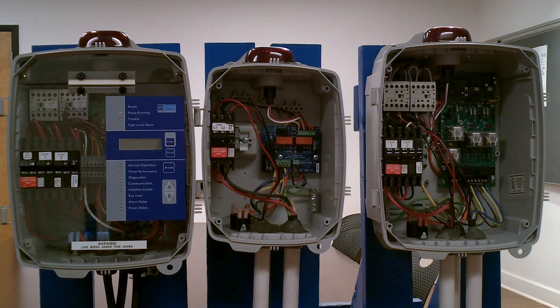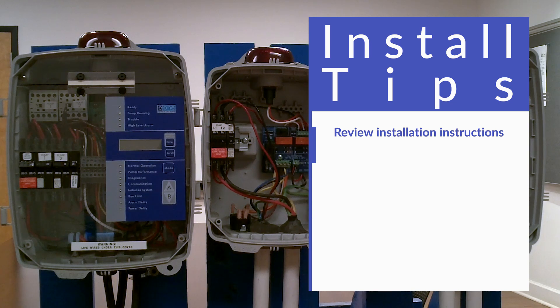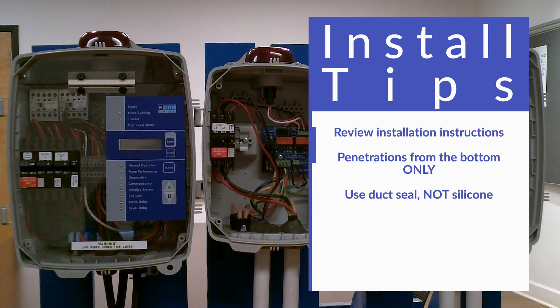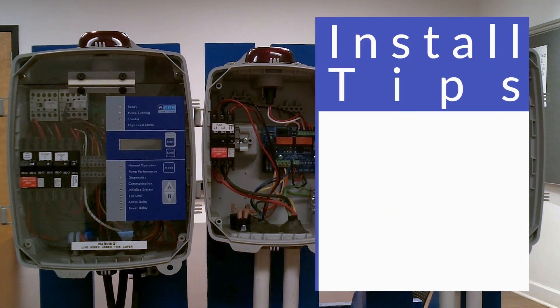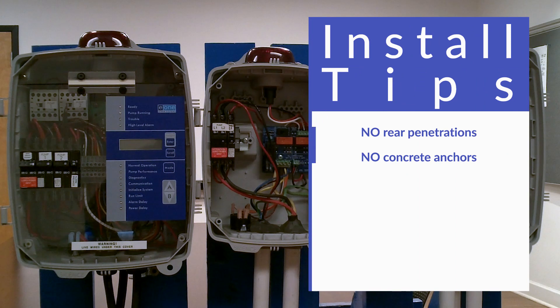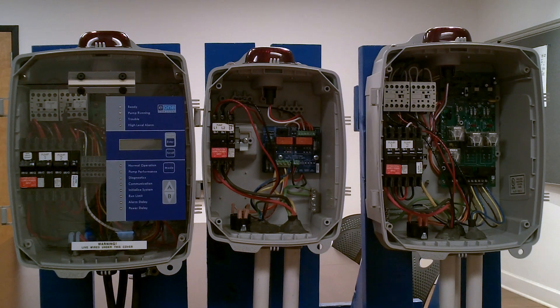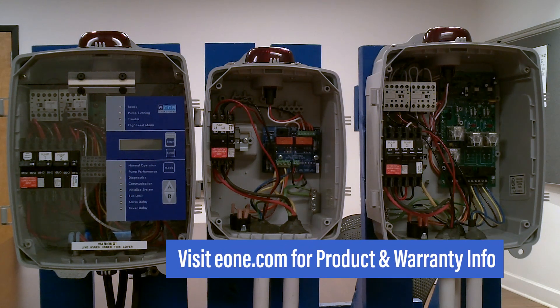Just a few things to note about any E/One alarm panel. Please take time to go through the E/One installation instructions that can be found on eone.com — it's going to cover the installation techniques, which will also be covered in future videos. Biggest things to note: penetrate the panels from the bottom only, use duct seal not silicone, don't come through the back, and don't use concrete anchors. These things will void warranty and change the way the product performs in the field. So be smart about your installs and use the available literature.